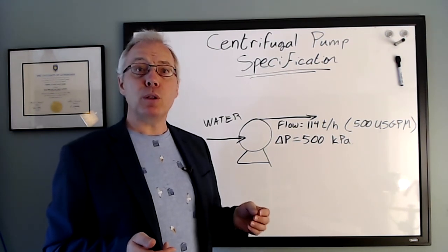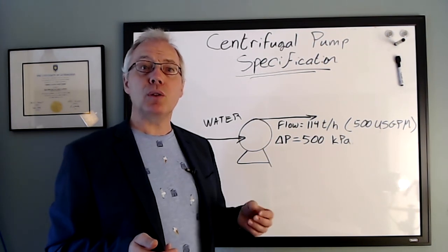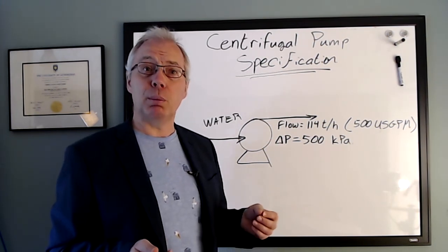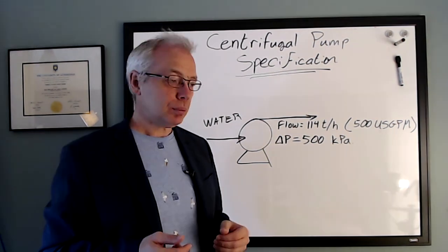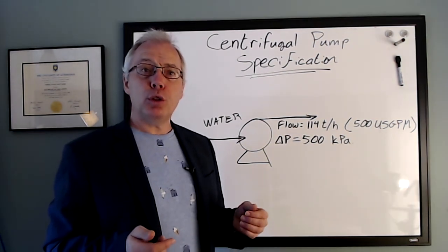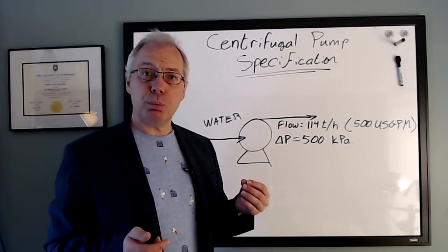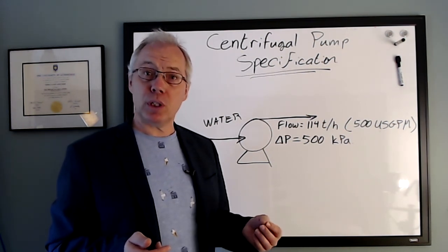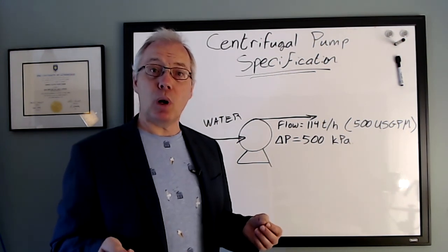It would be prudent for me to check with the civil, mechanical, and piping disciplines to see if a multi-stage pump would impact their work. I would only choose a multi-stage 1800 RPM pump if something prevented the simpler 3600 RPM pump from being feasible. We will cover that topic in the next video.